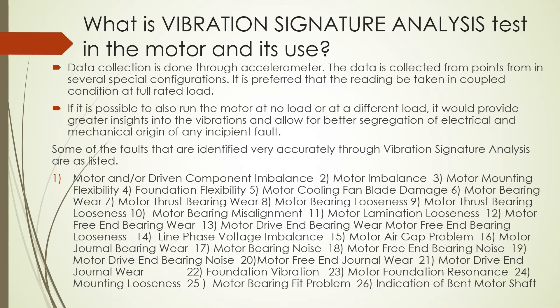Faults accurately identified through vibration signature analysis include: motor and driven component imbalance, motor mounting flexibility, foundation flexibility, motor cooling fan blade damage, motor bearing wear, motor thrust bearing wear, motor bearing looseness, motor bearing misalignment, motor lamination looseness, motor free-end and drive-end bearing wear and looseness, line phase voltage imbalance, motor air gap problem, motor journal bearing wear, motor bearing noise, motor free-end journal wear, motor drive-end journal wear, foundation vibration, motor foundation resonance, mounting looseness, motor bearing fit problem, and indication of a bent motor shaft.